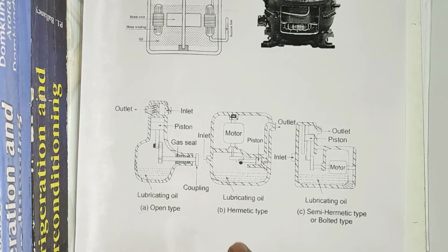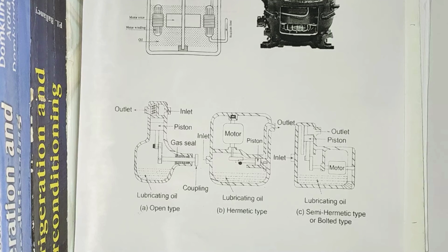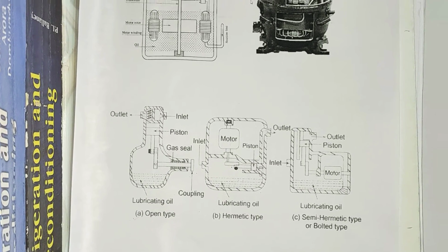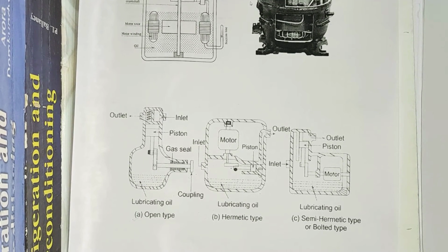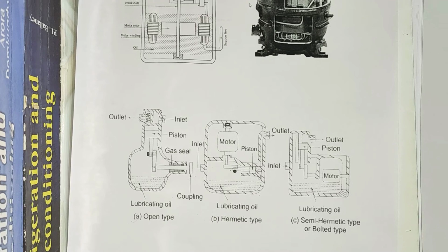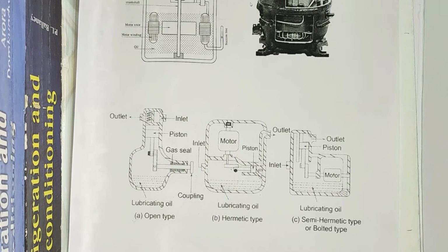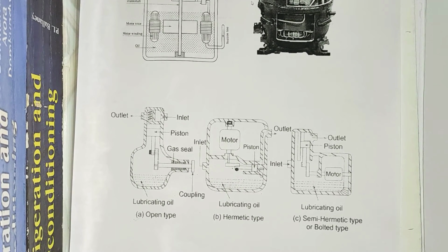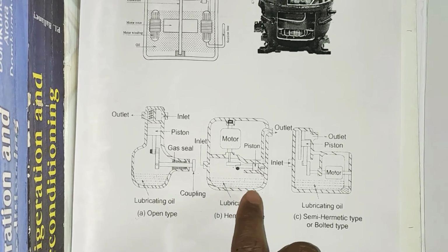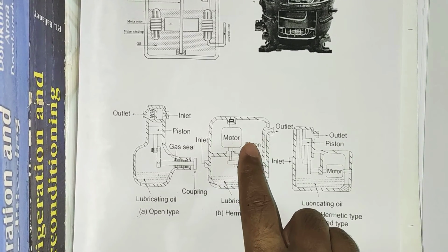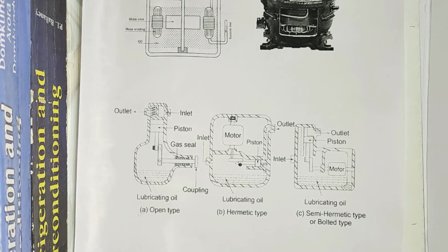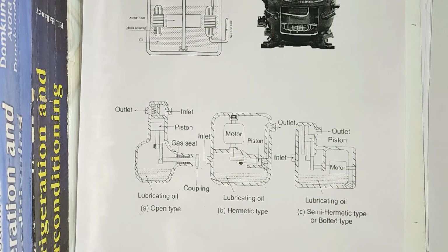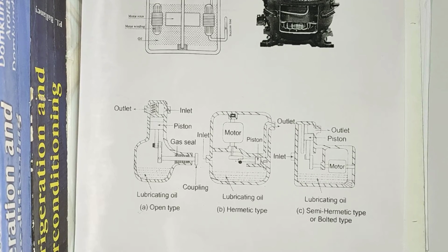One drawback is that these hermetic compressors are not serviceable. They are also not so flexible, as it is difficult to vary their speed to control the cooling capacity. Now, in some large capacity hermetic units, the cylinder head is usually removable so that the valve and the piston can be serviced nowadays. For large units, the cylinder head can be removable.